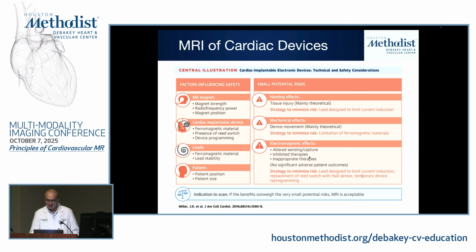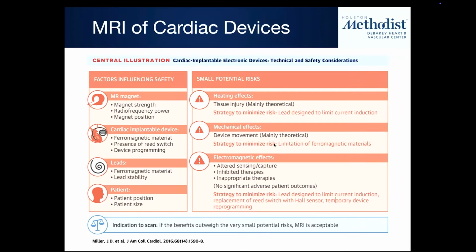The other is obviously mechanical effects. Could this device move? I implanted something, could it move? And then the third would be electromagnetic effects, where the device itself causes an electromagnetic field. That could cause problems, where it could cause excitation to the patient, or it could cause pain. So these are things that you need to be aware of.